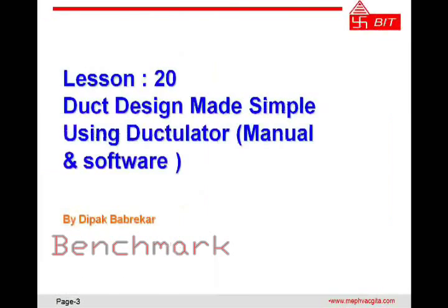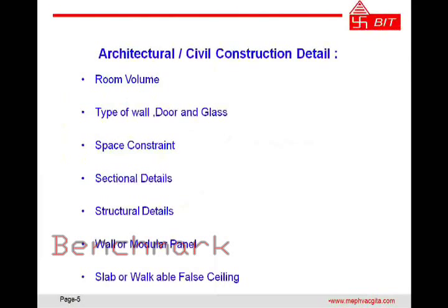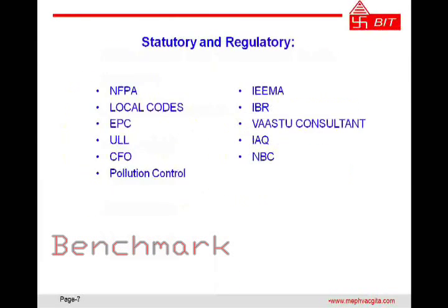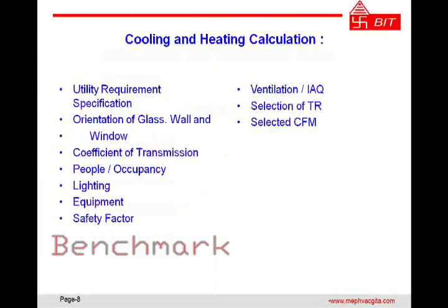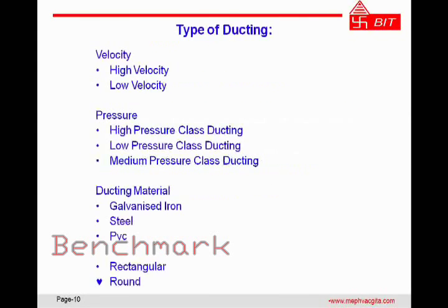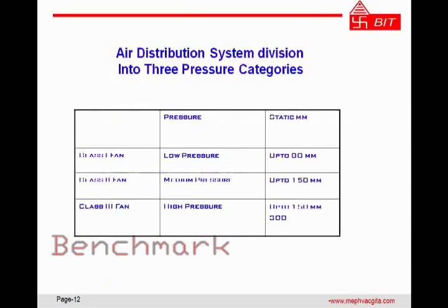In this section, Lesson 20, we are going to see how ducts are designed with manual ducting and the software ductulator. We are using standards and regulatory codes. As we have already seen in the cooling load calculations, we get the tonnage and CFM for design stages. We also need to determine the duct depth in coordination with other services, using low pressure ducting with the equal pressure method.